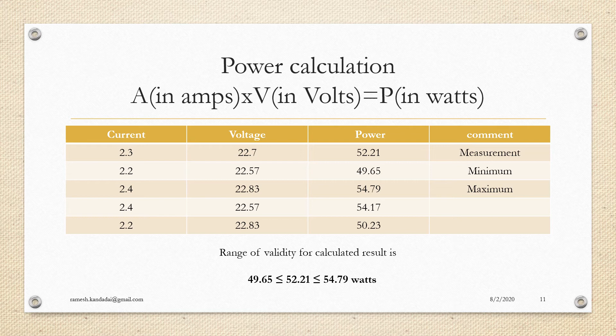We find that the total range of the power is around 5.14 watts. Based on the measurement and calculation basis, this is just under 10% of the measured calculated value. This is not a good result because acceptable levels of error in measurements should ideally be around 3%.